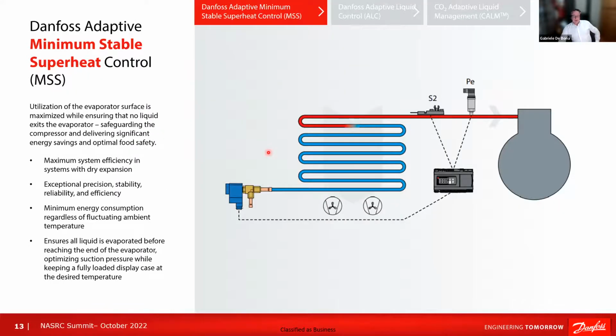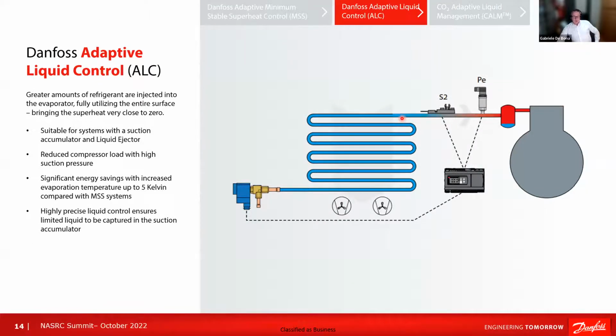Here is a different way to explain it. With the minimum stable superheat, you see that the evaporator is driven at its best, but of course, a last part of it is used to make sure that all the fluid is evaporated and only vapor is going out. With adaptive liquid control, on the contrary, the full evaporator is utilized, and a very small portion of bubbles can go out of it, which are collected in a small liquid receiver just before the compressor, and then the liquid ejector will take care of them and make them recirculate into the system.